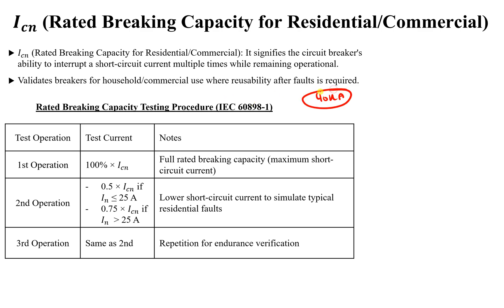The first test applies 100% of the fault current — 100% of 40 kilo-ampere in this example. This represents the maximum possible short circuit current, which is the ICN rating for the breaker. The second test applies 50% of this value if the rated breaker current In is less than or equal to 25 ampere, or 0.75 of the short circuit value if In is greater than 25 ampere.